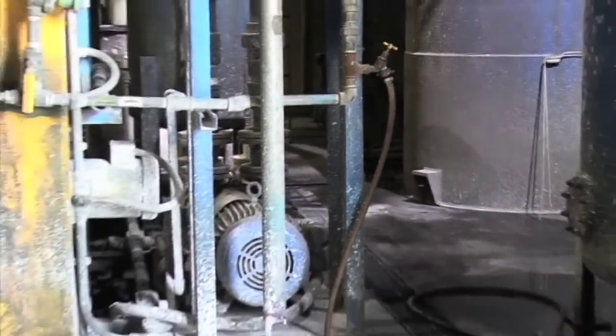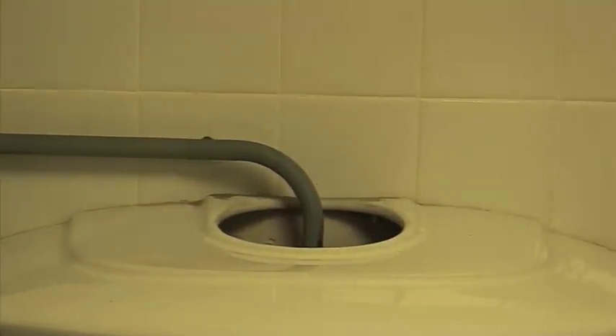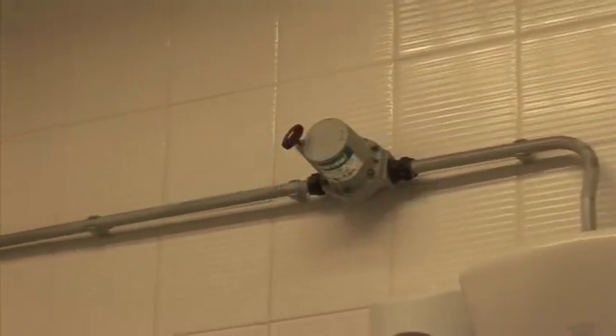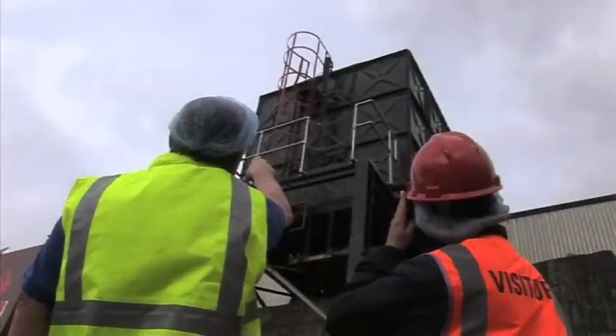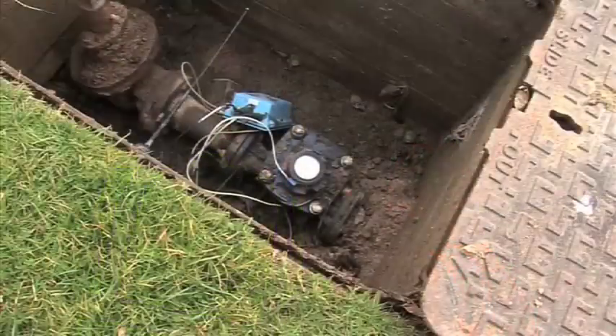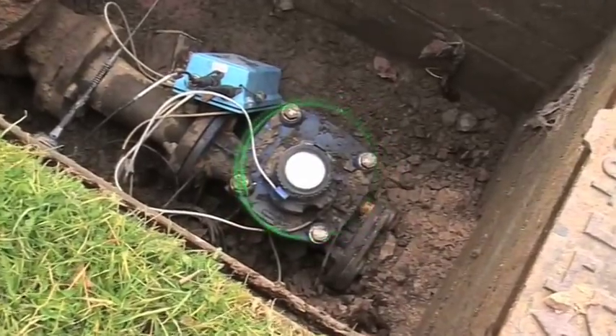Contamination and waste are rightly the main focus of the day-to-day work of the regulations inspectors. But inspectors will also be looking for the misuse of water — for example, where the energy or water pressure of the mains is being used to provide motive power or electrical generation. You often find urinals without flow control installed, flushing frequently and unnecessarily — this would come under the undue consumption regulation, and a simple timing device is all that's needed to solve the problem. On-site inspections combined with regular mains network checks using sophisticated flow monitoring can highlight unusual water usage that doesn't match the meter readings — likely a breach of the erroneous measurement regulation, a sign that the meter has been bypassed and the water, in effect, is being stolen.